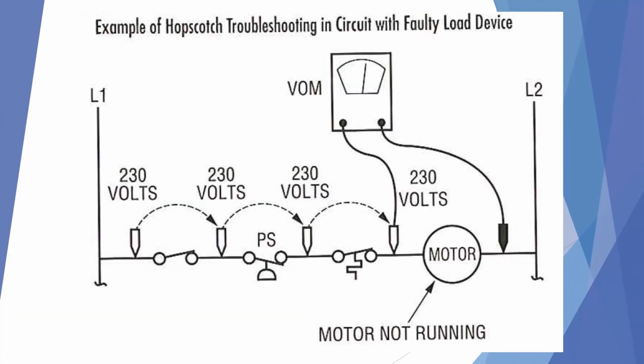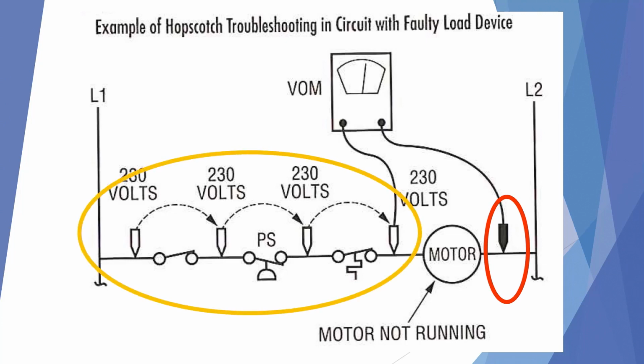A common method of troubleshooting this type of situation is called the Hopscotch troubleshooting circuit method, where you put one probe of your voltmeter on one side of the load and then take the other probe to the other points throughout the system to find out which switch is open, causing the motor not to run.